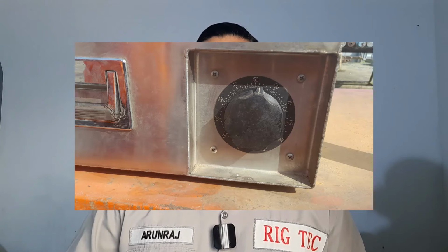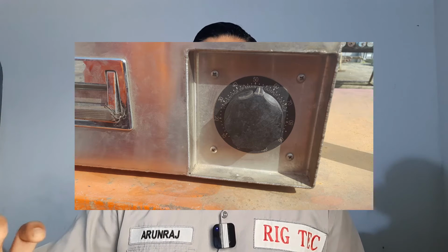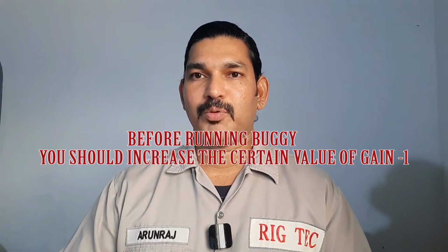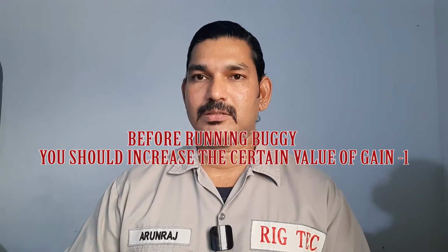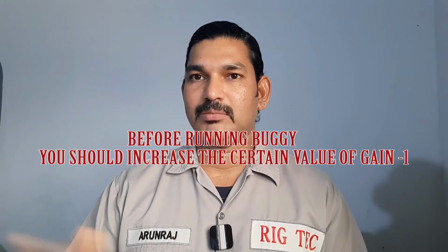And give the appropriate mag current. You can increase or decrease the mag current through that variac. Variac means a magnetic control. There is a control on the right side of the console. If you rotate forward, it increases the mag current. If you rotate in reverse, the mag current will decrease. So give the appropriate mag current, 2.5, 3.5 or something.